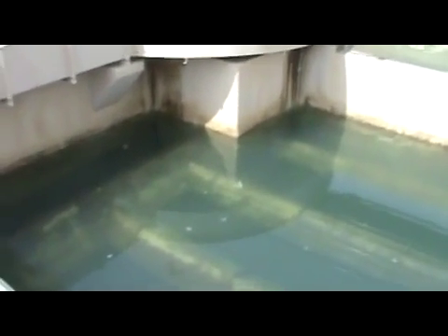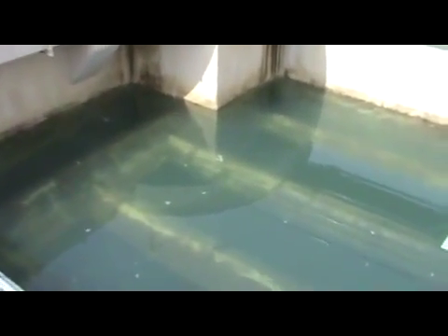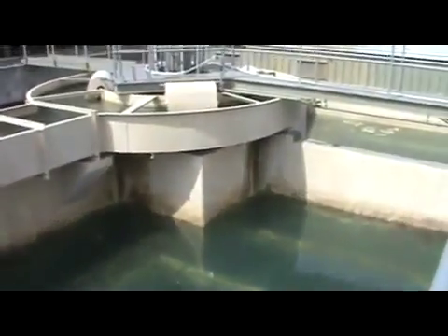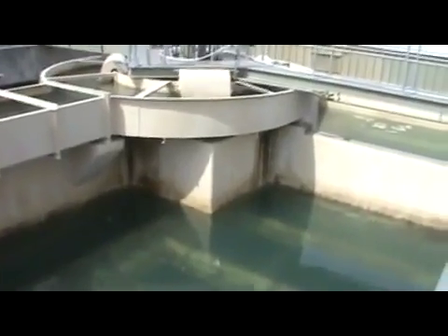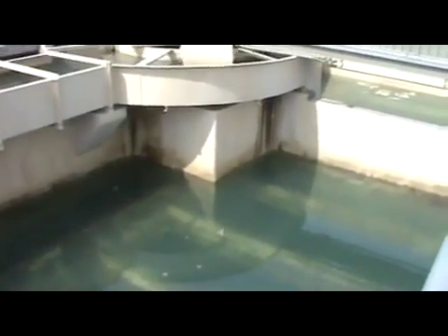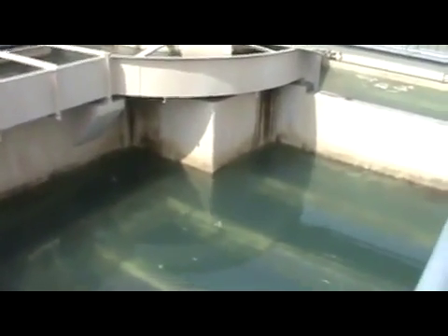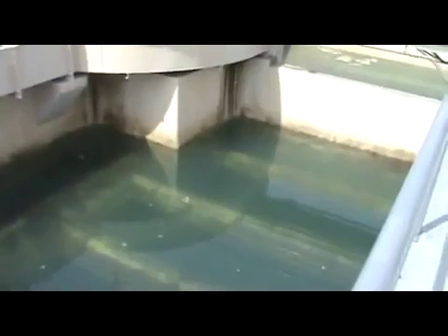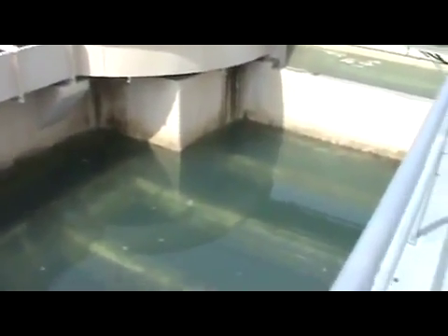Then valves open up on the bottom of the filter, and air and water begin to be injected into the filter from the bottom side. So instead of things flowing down from the top, that's why it's called a backwash. You're washing from the bottom back up, and it expands that filter bed material. As that filter bed material expands, remember I said the filter was drained down, so these troughs you see are actually right above the skim of the water level.